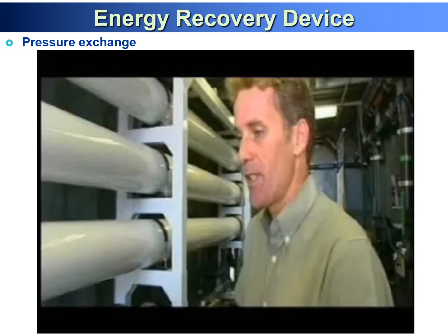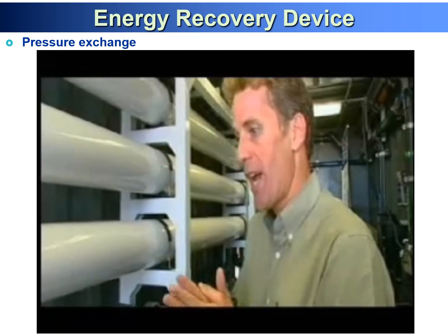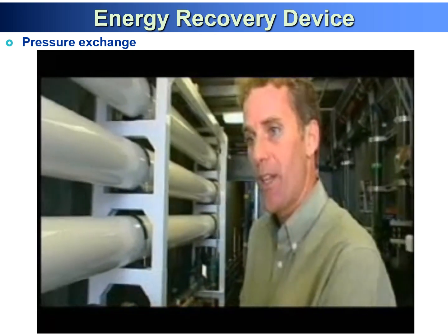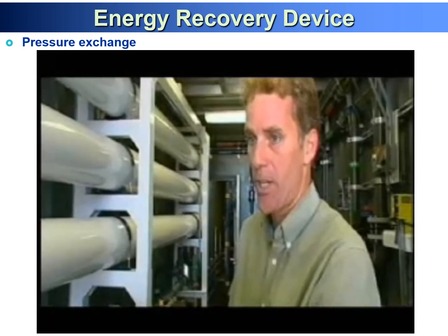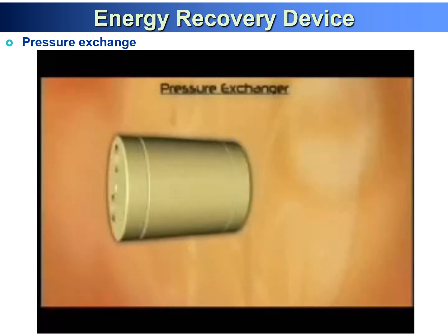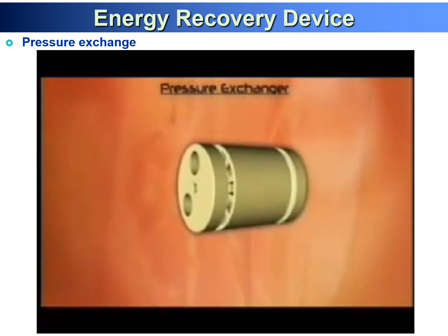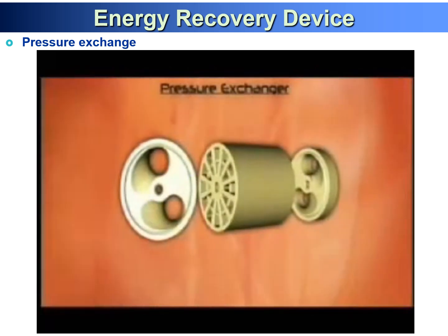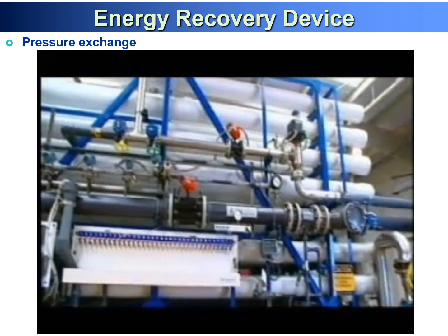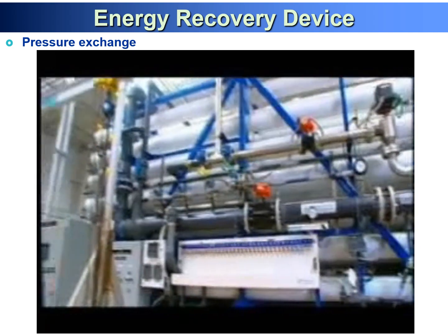With old desalination systems, you used to have to pump 100 gallons a minute to get 40. With the new desalination systems and this pressure exchanger technology, you pump 40 gallons a minute and you get 40 gallons a minute. It's amazing. Yes, it really is that amazing. Just a ceramic cylinder capped at either end by fixed propeller-like end ducts, and all precision fitted inside a tubular housing. The pressure exchanger is effectively cutting running costs by more than half.